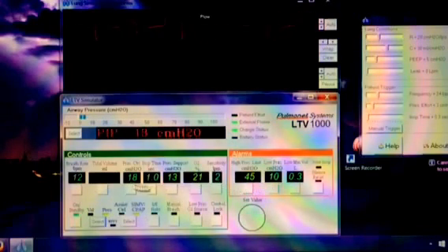When we switch over to pressure control, all of a sudden this tidal volume is dim and the pressure control number is illuminated. The ventilator is still going to try to give 12 breaths per minute. But what is different is that it doesn't care how much volume they get — what it cares is that the pressure does not go too high. In this case it's 18 centimeters of H2O, meaning it's going to give 18 of pressure for one second. You can see up here on the waveform, they're going to get that 18 with every mandatory breath.